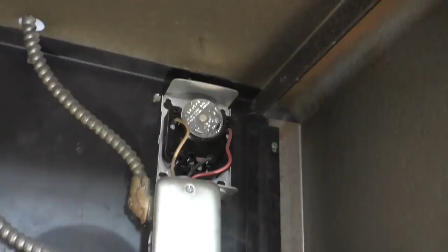So what that's going to do for you is it's going to cause an over-temp situation. What's actually happening is this safety switch here, up here, it has a little wheel in there. Take this off, there's a little wheel there. And that's attached to a bimetallic coil that's inside the plenum area. And as that reaches, there are three set points. The first one is fan on. So when it reaches about 125, 150 degrees, it kicks on the fan.